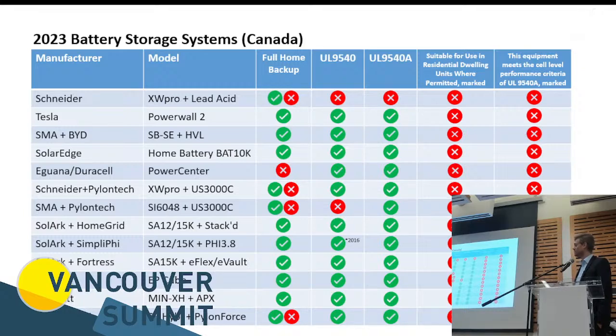Schneider with Pylontech, which we can also see in your cabinet, that combination is UL 9540A and 9540 certified, very, very popular. The SMA system for off-grid does not have it, because the battery has the UL 9540A, but not the system. SolArk is popular in some provinces together with HomeGrid. That is fully certified. With SimpliPhi, it's only certified to that 2016 code I mentioned earlier, so it's technically not certified. Fortress has an option with SolArk.